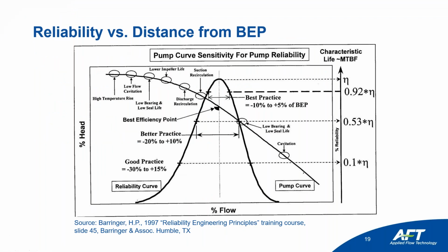This is a useful curve that plots essentially the same pump curve with those problem areas, but it shows another curve. This is your reliability curve right here. And so what you want to be is within this area of flow. So you want to be within this flow range of your best efficiency point. That's your allowable. Best practice is to stay within this range right here. As you start to operate further out on this bell curve, your reliability dramatically decreases on both sides, for low flows and high flows. So this just superimposes what the reliability of your pump looks like on top of its pump curve. And as you can see, when that flow drops, it drops very quickly, and it's going to decrease your mean time between failures. So that's a useful graph to conceptually keep in mind.